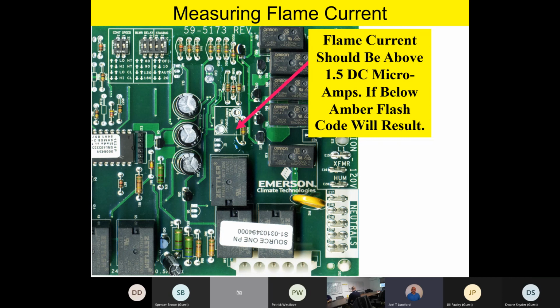Typical flame current, normal flame current, generally runs about 3 to 4. If you take a look at your install manual, I think it says 3.5 or 3.7 is normal. But from my field experience, and hearing technicians in the field measuring flame current all the time, it typically runs about 3 to 4, based on the quality of the ground, if the flame sensor is clean, if you have proper gas pressure, a good solid flame, and a good clean ground. But just remember those key points. 0.1 is lockout. At 1.5, you get an amber flash code telling you it's starting to get low. And typical flame current runs about 3 to 4.